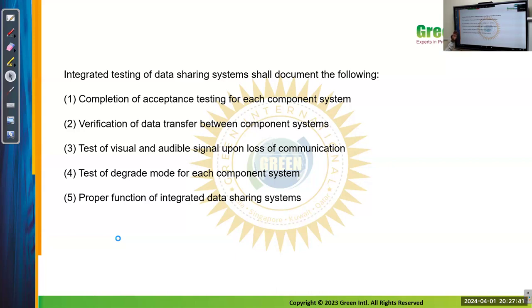So each data transfer, whether it is happening in the PLC system or not, we have to verify. Test of visual and audible signal upon loss of communication. If there is any supervisory control, like in high-rise buildings, they have to communicate from a remote area and direct it. Test of degraded mode for each component system. Proper functions of the integrated data sharing system. So these are all the testing items that shall have documents once the testing is completed. Before handover, these are all the documents we have to submit.